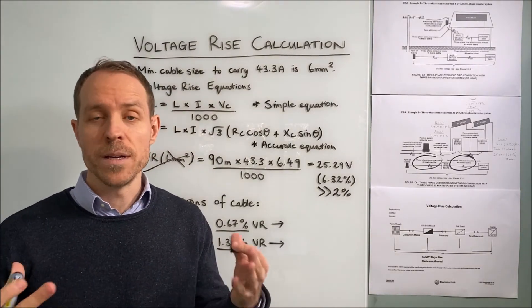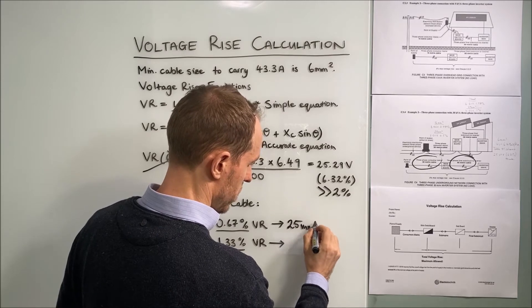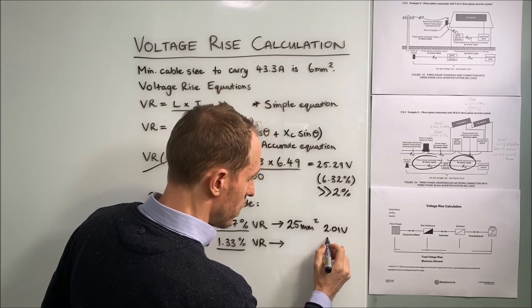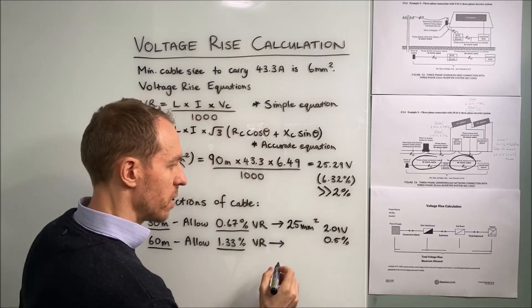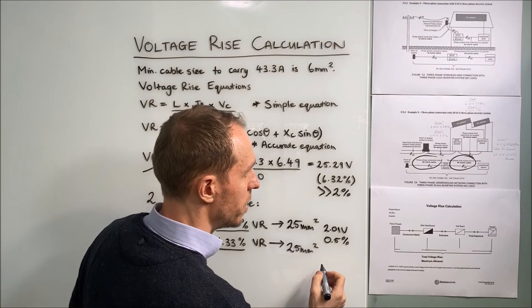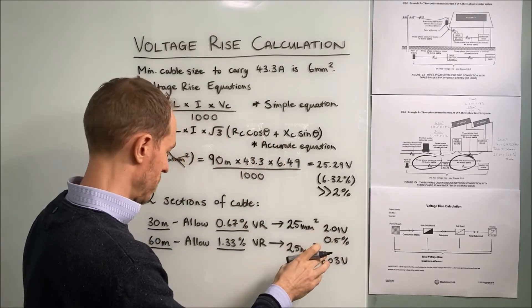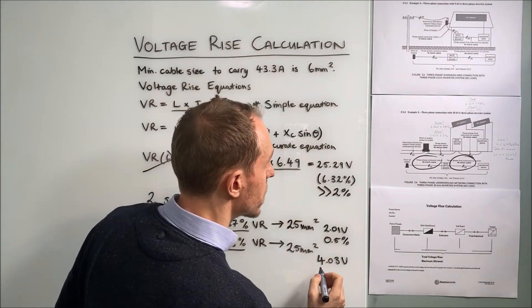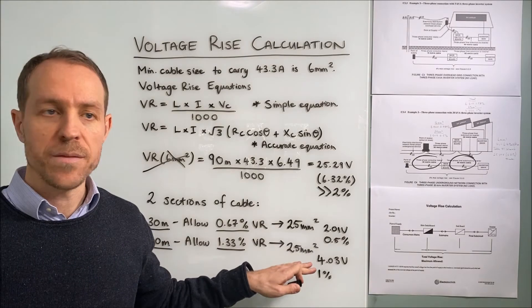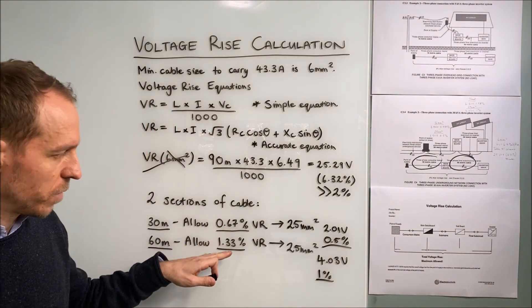So if we go to 25 square millimeters cable for the first section, our voltage rise calculated by hand is 2.01 volts or 0.5%. For our second section using 25 square millimeters, the calculated result is 4.03 volts, basically double, of course it's double the length, or 1%. In both cases, if we use a 25 square millimeter cable, both of these results are under our allowable limits for the sections.